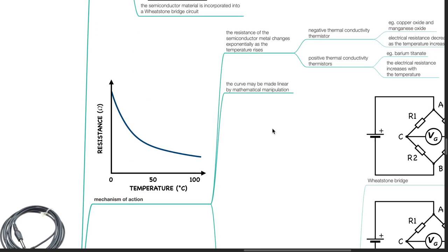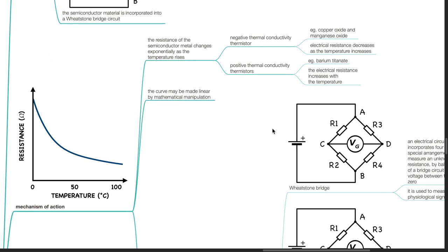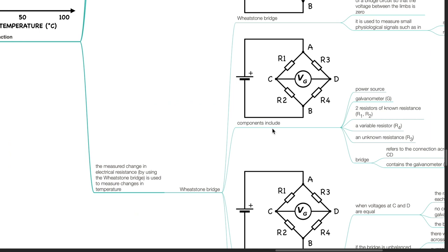Mechanism of action of a thermistor: the resistance of the semiconductor metal changes exponentially as the temperature rises. For a negative thermal conductivity thermistor such as copper oxide or manganese oxide, electrical resistance decreases as temperature increases. For a positive thermal conductivity thermistor such as barium titanate, the electrical resistance increases with temperature. The curve may be made linear by mathematical manipulation. The measured change in electrical resistance using the Wheatstone bridge is used to measure changes in temperature.